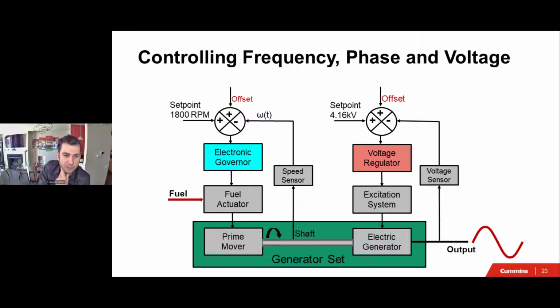So now putting the two together, if this is my generator, this is the prime mover, which is the engine, real power, and this is the electric generator, and they're all connected on the same shaft, they're coupled together, and I get the AC output voltage with three-phase voltage. Basically, I have two set points, and then I change that offset. So that's what the control is doing.